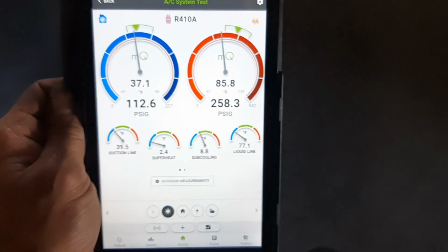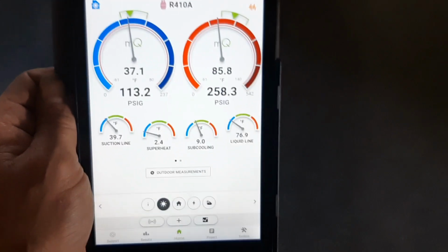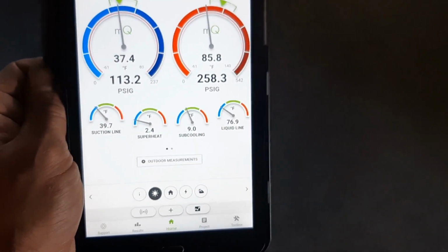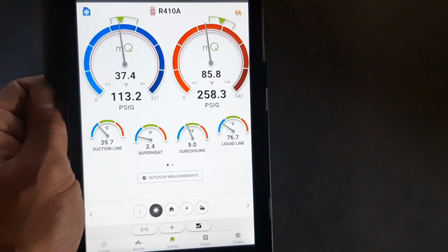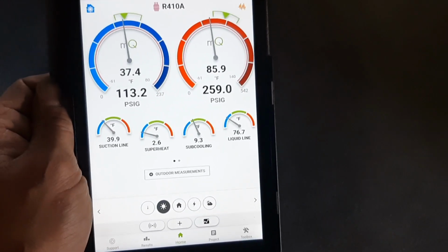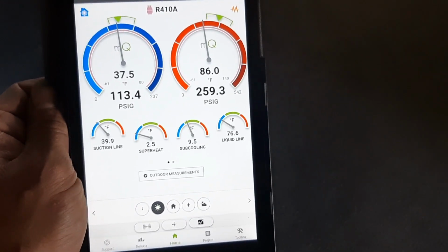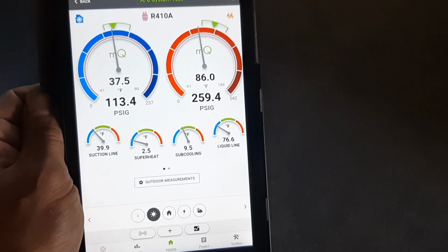So, might try to get rid of this zone system whenever we change this equipment out. Let's see if that superheat improves with the other side open now, but that's getting way too close to flooding that compressor. Of course, with the way they installed it, it's going to have a shortened life anyways, so doesn't look like it's going to freeze up, but we may flood that compressor if one side's only calling.